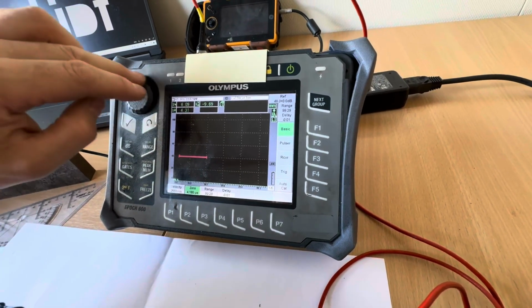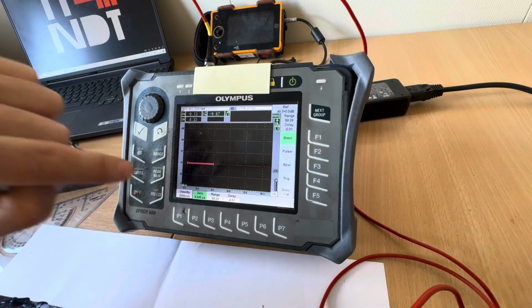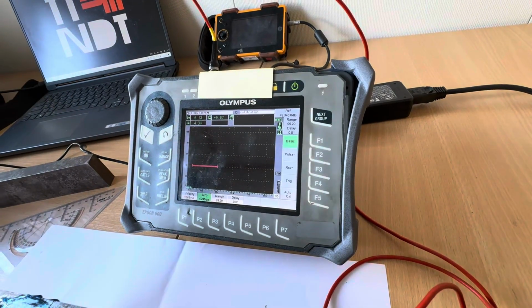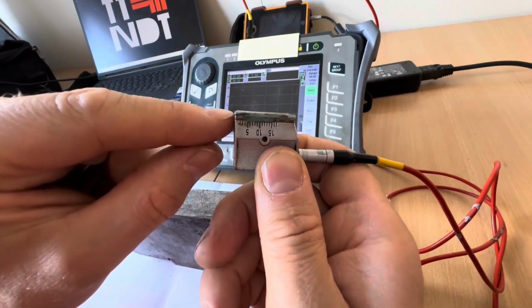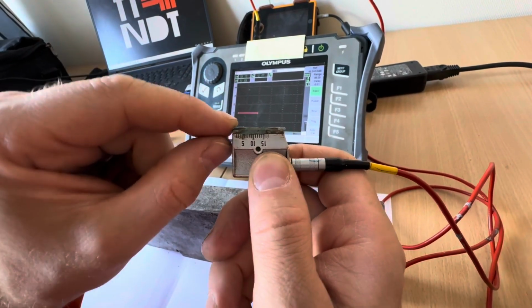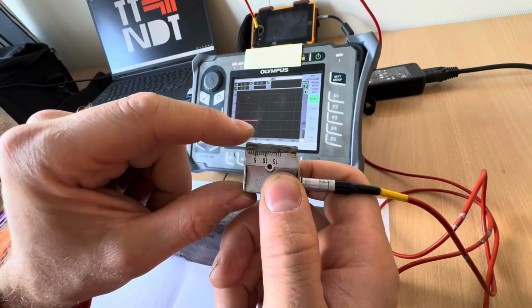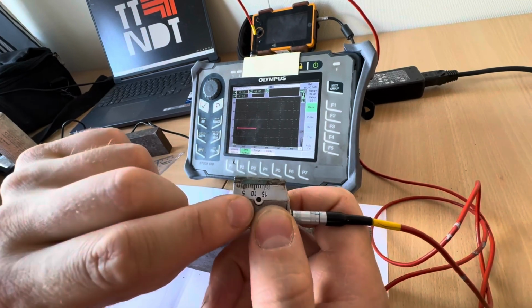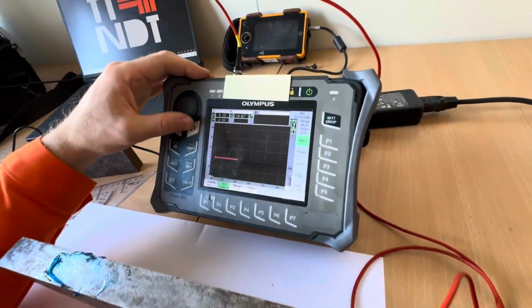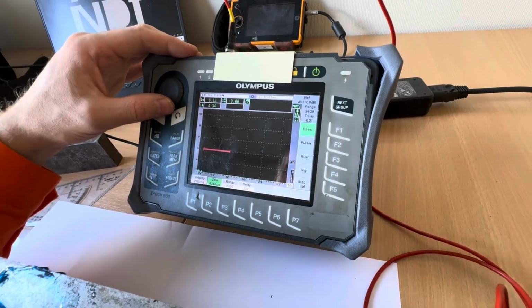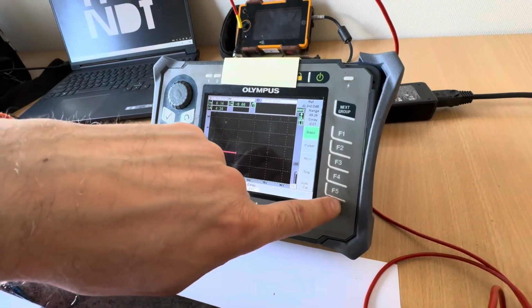So, distance 0, velocity is the speed at which the signal is sent, and 0 is the distance, specifically the shoe. It will change depending on whether it's glued or not and what the thickness is. That's why we need to adjust it so that this value changes. What we're doing now is intentionally changing it.